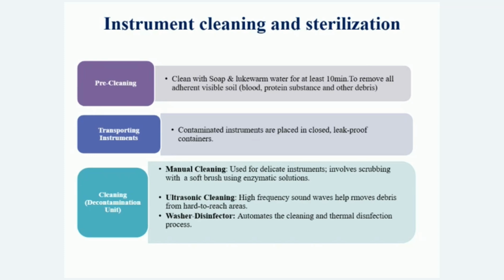Contaminated instruments have to be placed in closed leak-proof containers. And manual cleaning has to be done for delicate instruments using a soft brush with enzymatic solution. In hospitals, cleaning is done in the CSSD. So the preliminary washing for removal of soil, the blood should be done so that it doesn't dry up, and then it has to be sent to the CSSD.